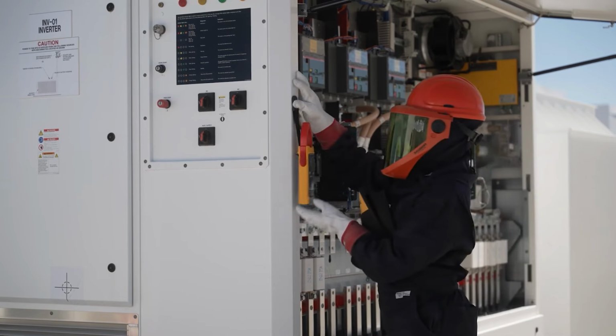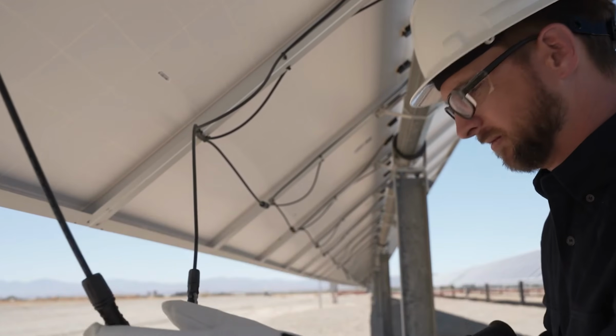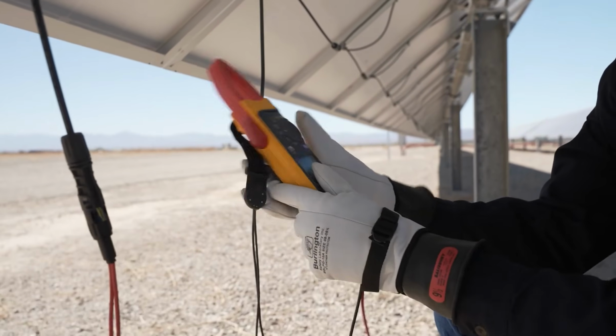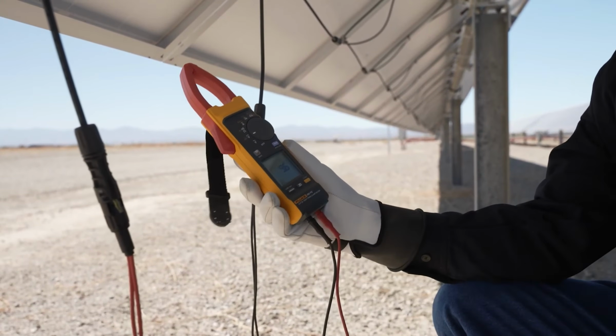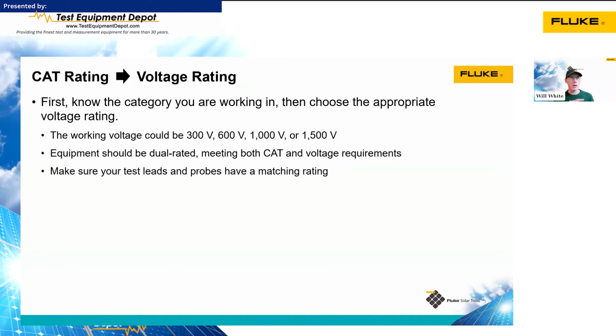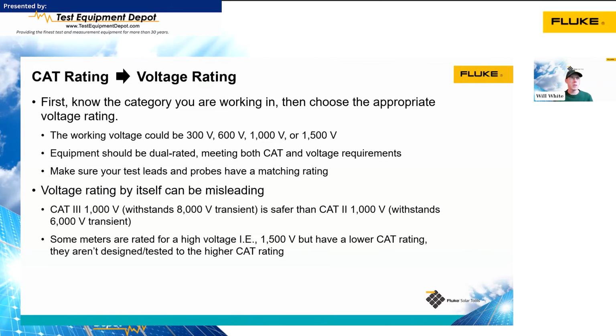Another important thing is the last bullet on the slide. Currently, we need to make sure that our meter leads are also rated at the same or greater rating than what our meter is rated for. So we have a meter, the 393. It's a category 3 1500 volt rated meter. It comes with category 3 1500 volt rated test probes. But if they were to be damaged, you might want to take a test lead off of a different meter, and maybe those test leads don't have that same rating. So they might be category 3 1000 volts, which are much more common. If you're testing on under 1000 volt system, that's fine. But if you're testing a 1500 volt system, those test leads would not be appropriate for use in that meter.